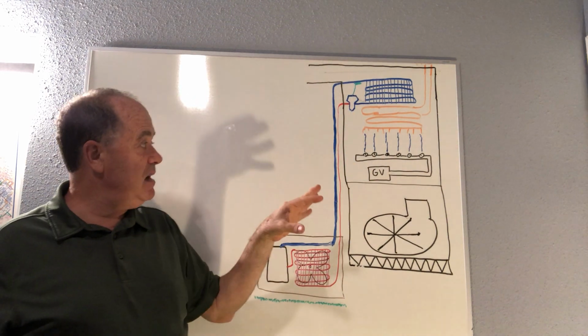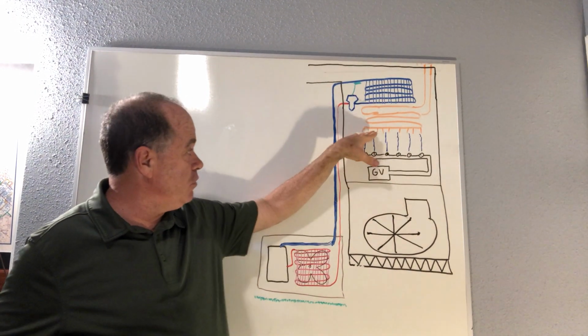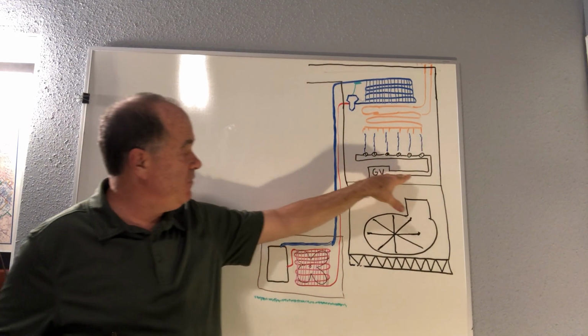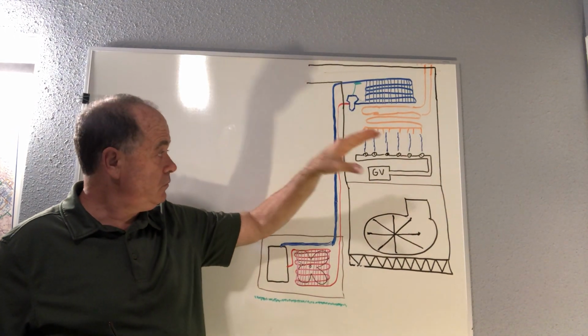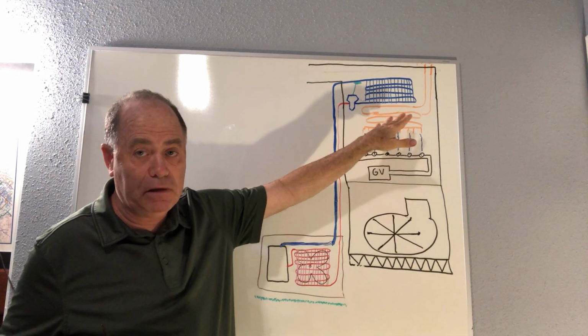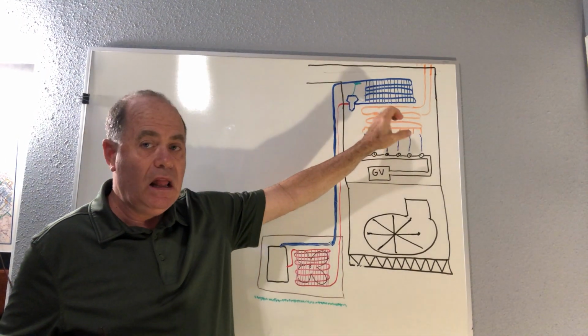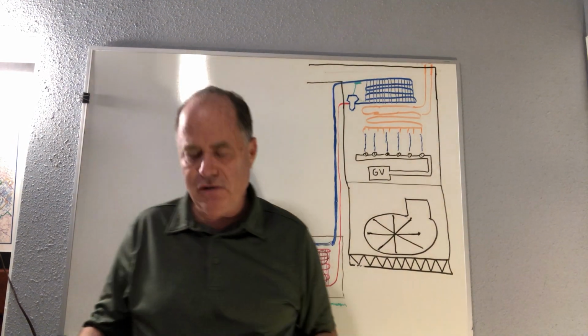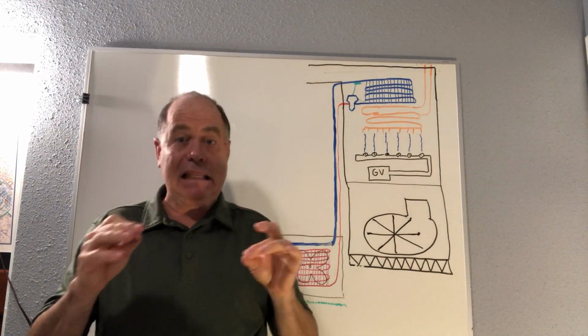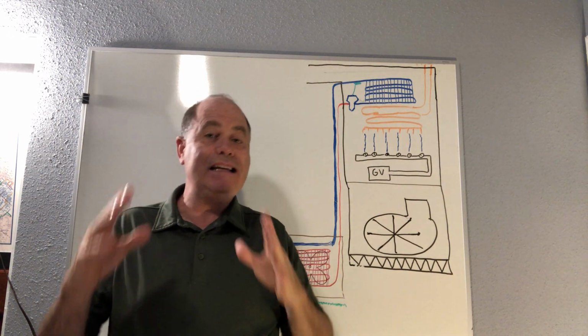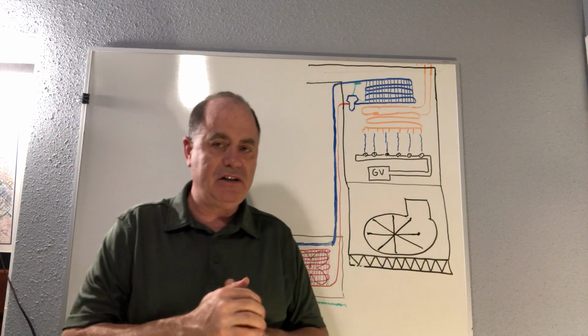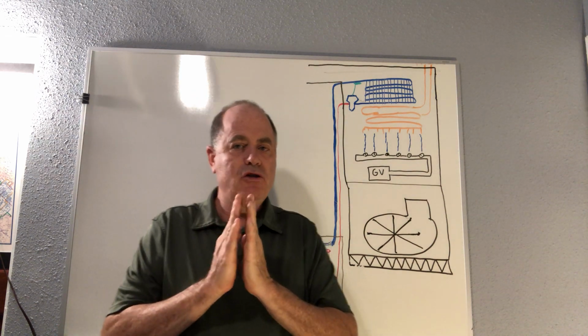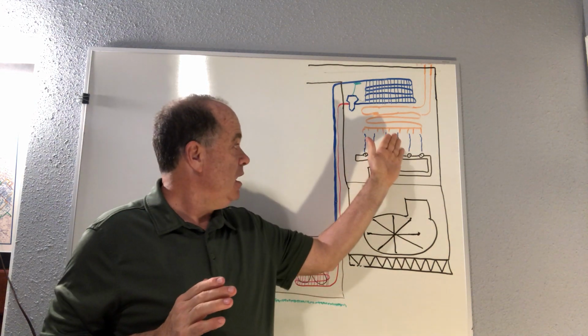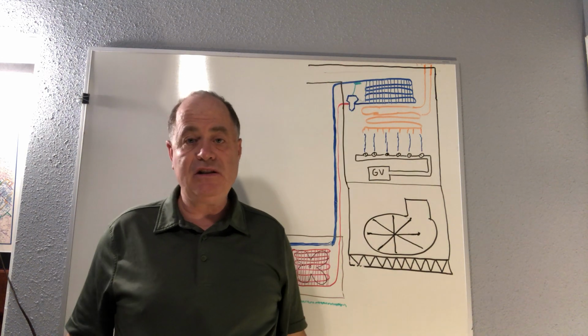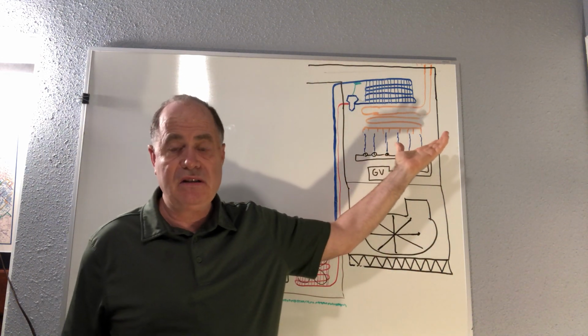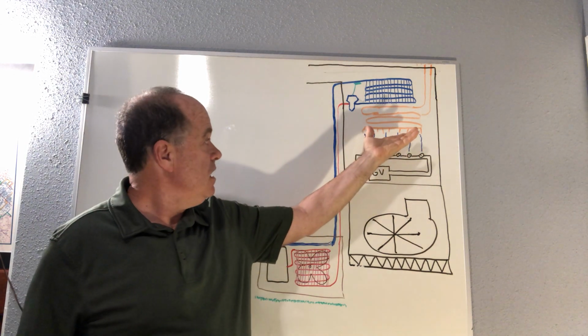The heat exchanger is metal that gets heated from the fire, and I've drawn this in blue. And we have the gas valve here that shoots the flame out and heats up the inside part of the metal. And then the metal, a lot of times, they don't clarify this in any books, the outside of the metal of the heat exchanger is what heats the air that you come in contact with. We have no direct connection between the fire and the air that you come in contact with, in centralized furnaces for homes or businesses.